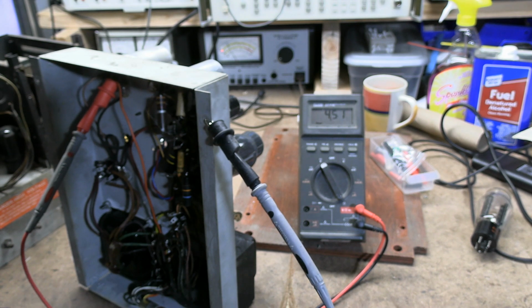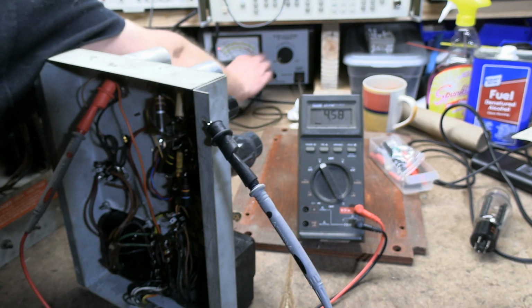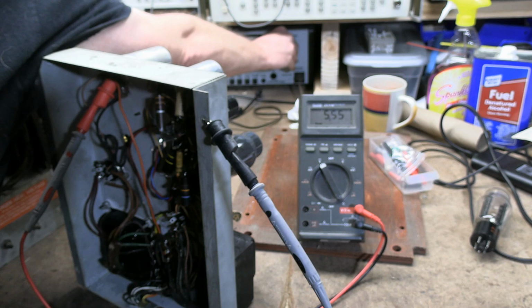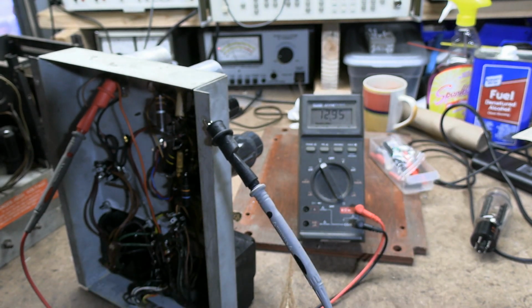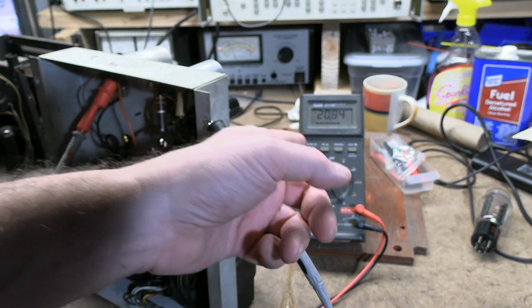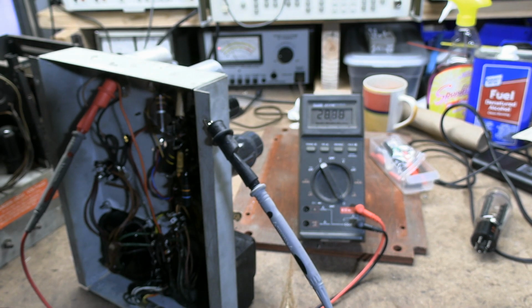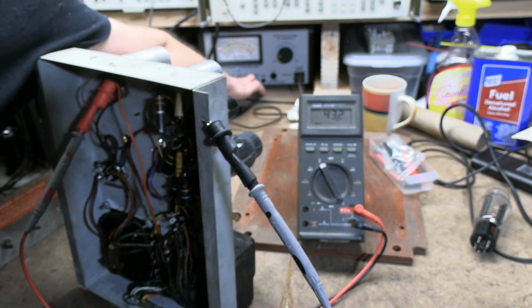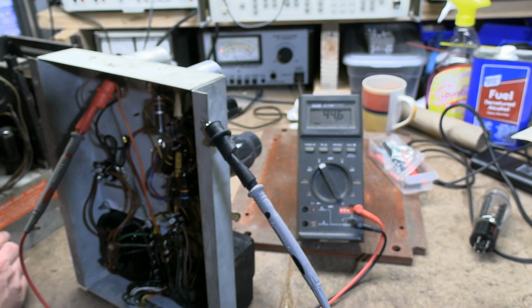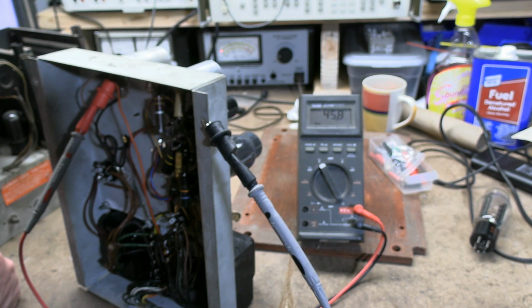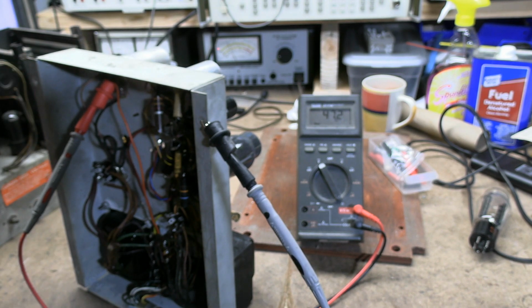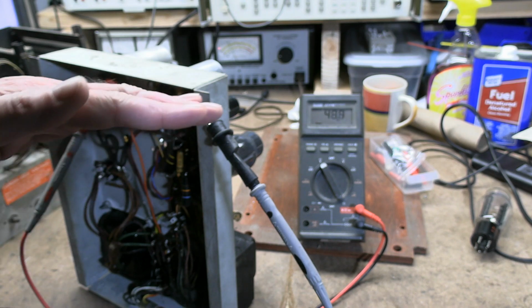Alright, well, I've been babbling. It looks like we've settled it at about 4.5. So I'm going to ramp things up a little more. And, of course, that's going to go up. So I'm going to keep doing this. I'm going to keep an eye on that voltage. It should keep going up and up and up, while the current only modestly goes up. Current draw of the entire set. So B+, we're getting up there. We're up to 40 volts already. And our current draw is 0.6 amps or so. So you get the idea. Just keeps, every time this plateaus, turn up the variac a little bit. Plateau, turn it up a little more.